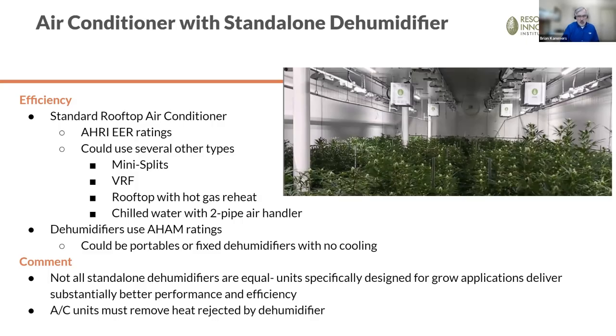And for the most part, these are limited in their capacity, severely limited in their capacity to do any dehumidification. So the need is there for other dehumidifiers in the room. They could be portables, and typically they are, or you could have some dehumidifiers that can reject the heat outdoors and really don't affect the cooling load of your regular comfort cooling air conditioner.